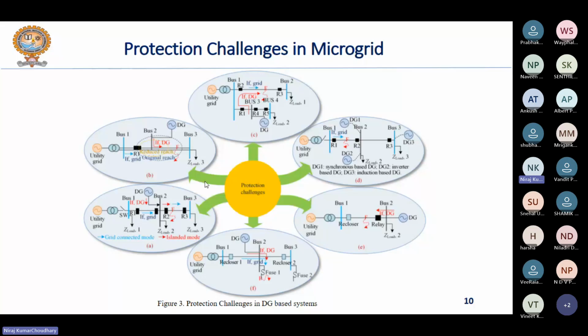The operation of reclosers is similar to circuit breakers, you can say, having a different duty. If any disturbance or fault occurs in the system, the recloser will open and close its contact for a few electrical cycles. If that disturbance or fault is removed automatically from the system by any means, then that was not actually a fault, it was a transient present in the system, and the system will operate in a normal mode, right? But if after a few cycles the fault is not cleared, then the layer of protection will be provided by your relay and circuit breaker combination combinedly, right?